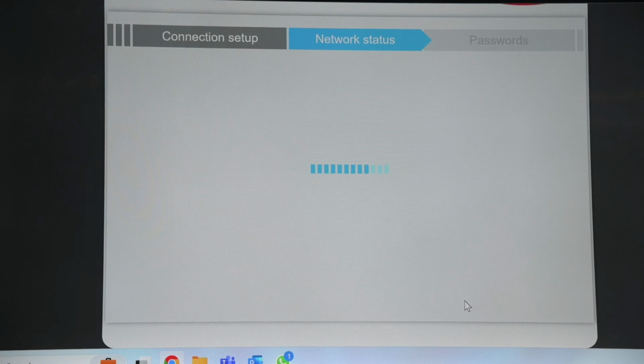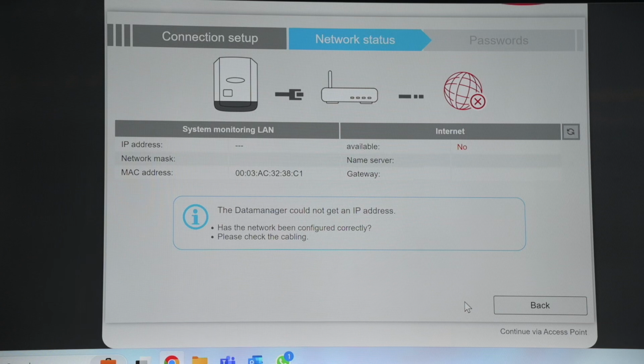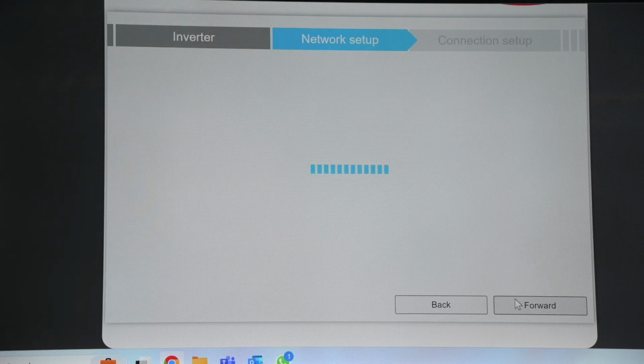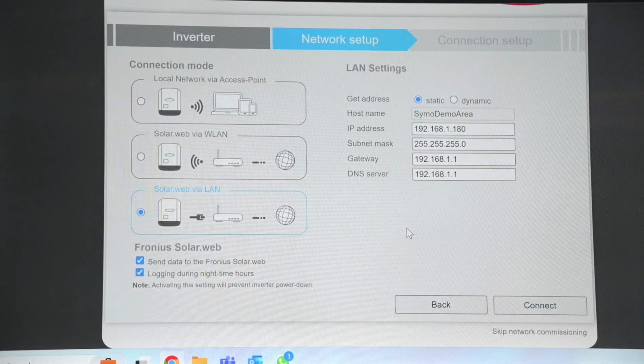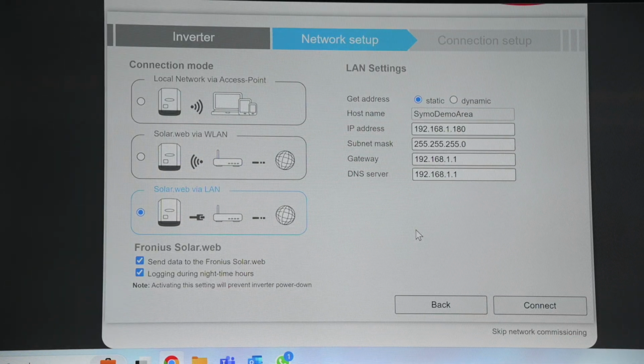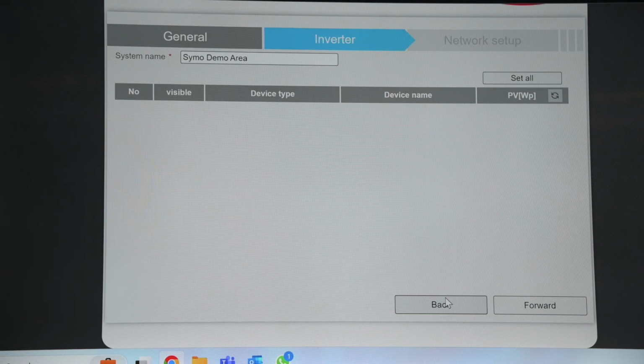Do you want me to touch on Modbus now, or? Yeah. Can you just go back to the network? Yes. Network setup. When there's no internet access at all, like a site that's maybe quite remote, is that where you go to LAN? Is that where you set your IP address? Correct, of the inverter, where you can modify it. If you've got an open port and a static IP assigned, then you can remotely log into the data manager. But again, only if you've got an open port is it possible. And Fronius doesn't take responsibility for any remote access. Yes, no, I understand that.